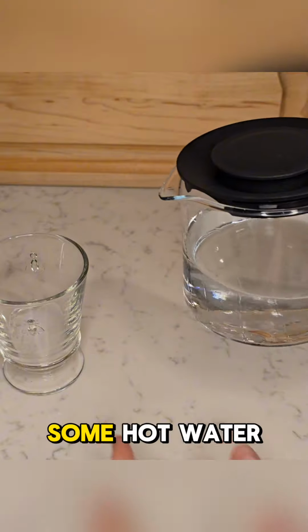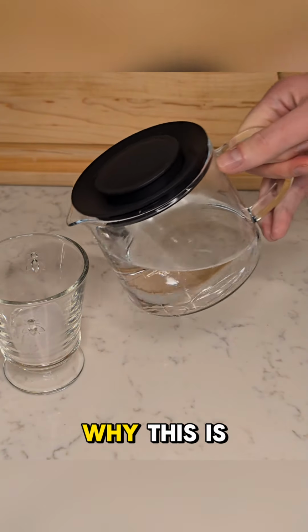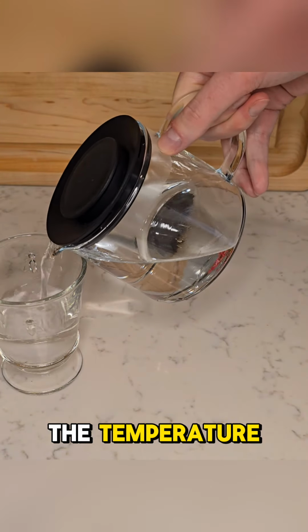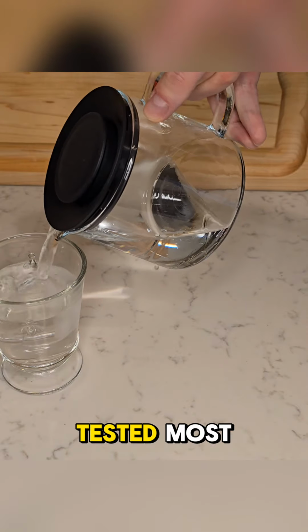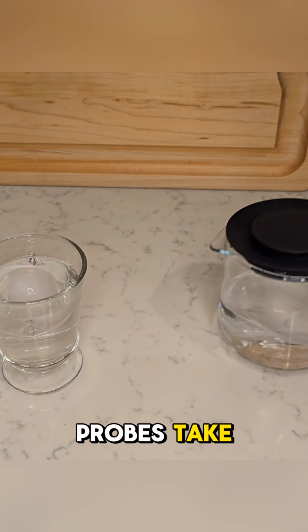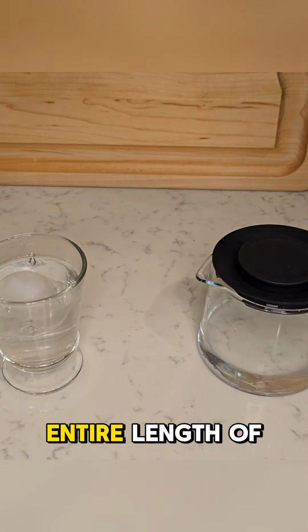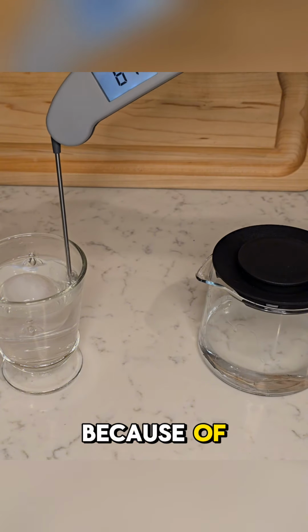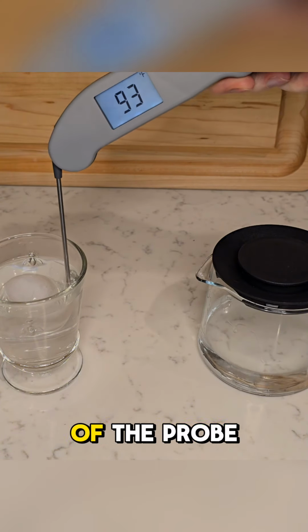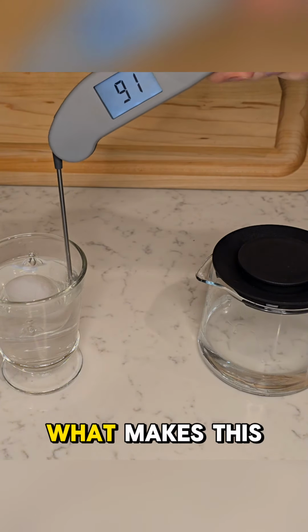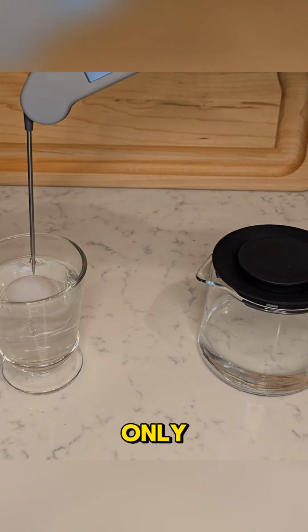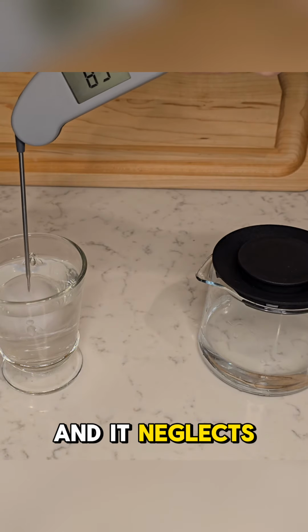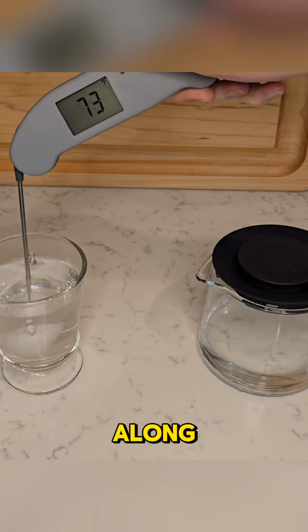Here I'm about to pour some hot water on top of the ice cube to show you why this is important. This allows you to measure the temperature profile through the medium being tested. Most other food temperature probes take the average temperature along the entire length of the measurement device because of thermal conductivity through the entire probe, since it's all metal. What makes this so special is that it measures only the temperature at the very tip and neglects the rest of the temperature along the length of the probe.